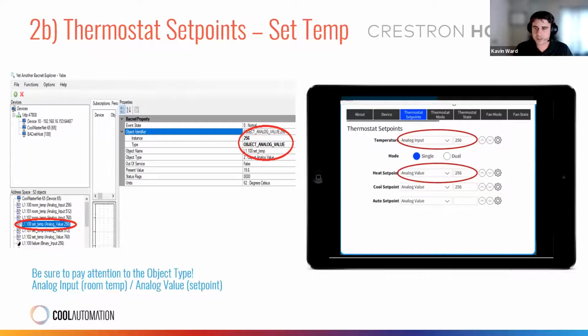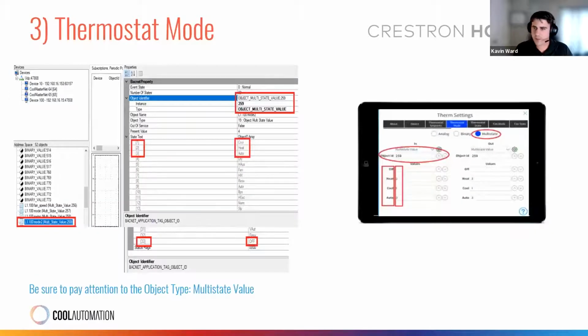The next tab on the Crestron Home side is the thermostat mode. On the object list from Yabe, find L1 100, whichever stat you're working on, and mode 2. Note there is mode and mode 2, so be sure you're selecting the right one, as they have different instance numbers. In this case, mode 2 equals 259, and it's a multi-state value, so be sure to select multi-state among the three options at the top: analog, binary, multi-state.